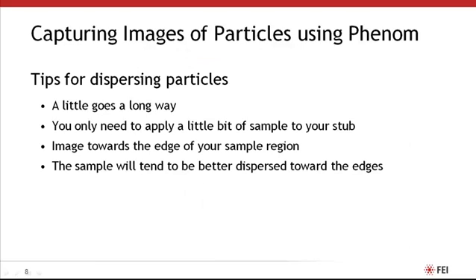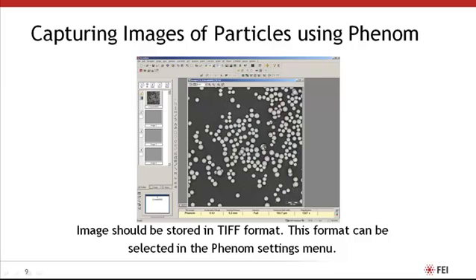Now that you've seen what a well-dispersed particle sample looks like, here are a few tips for how to prep the sample yourself. First, remember a little bit goes a long way — you need only apply a little bit of the sample to your stub. When you're done loading your sample into the Phenom, collect images towards the edge of your sample region, as the sample will tend to be better dispersed towards the edges. All images should be stored in TIFF format by going to the Settings menu on the Phenom User Interface and pressing the TIFF button near the bottom left-hand corner.